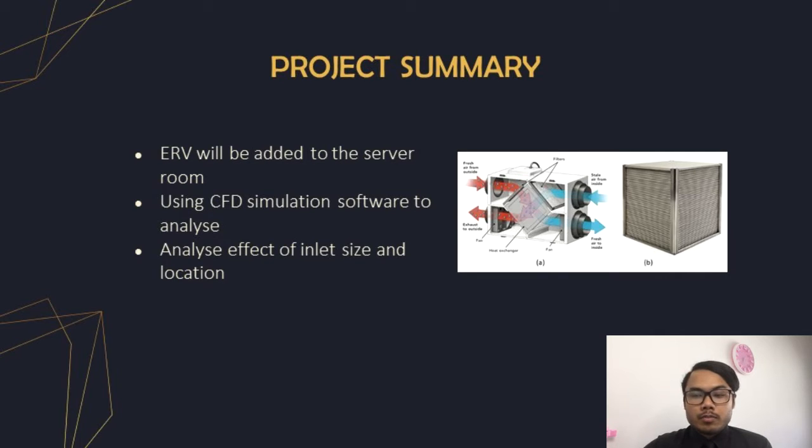The current server room is using a common split aircon system and causes high energy usage due to the high temperature of the room. So an energy recovery ventilator, or ERV, will be added for pre-cooling of the server room. This project is to see the difference in temperature when we add the ERV unit into the server room. Also, the effect of inlet size and location of the ERV will be analyzed using CFD simulation.